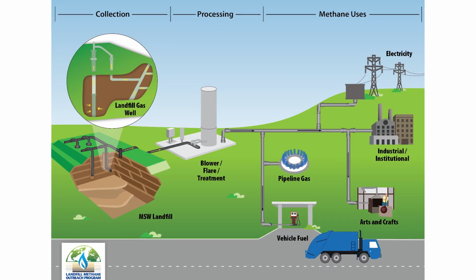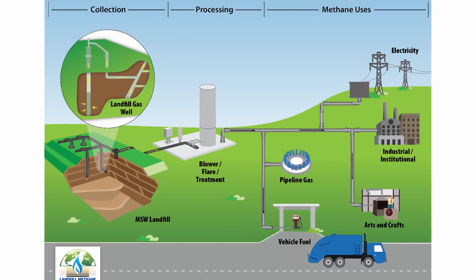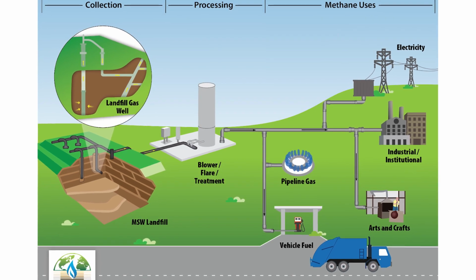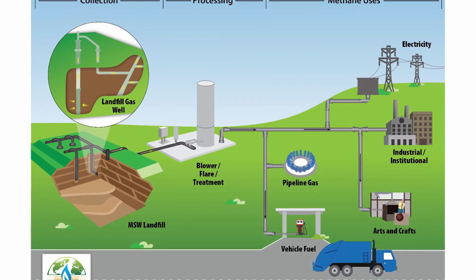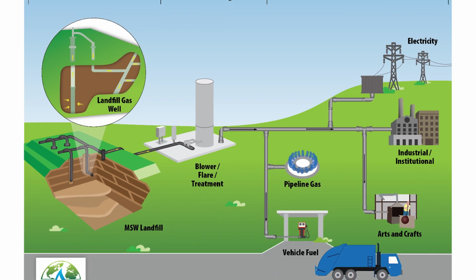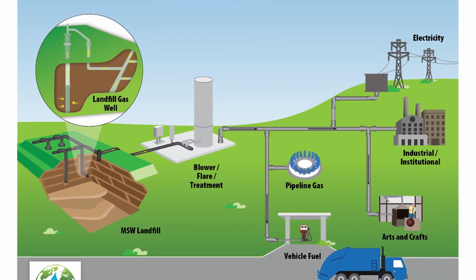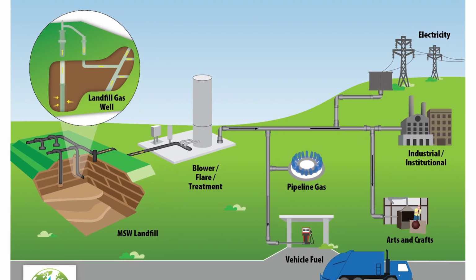We use the small line interactive UPSs to back up every PLC in the gas side of the landfill. They have generation, so they don't need long run times. They just need it to detect the outage, carry it through for approximately 30 to 60 seconds till the generators spin up and can carry the load again.